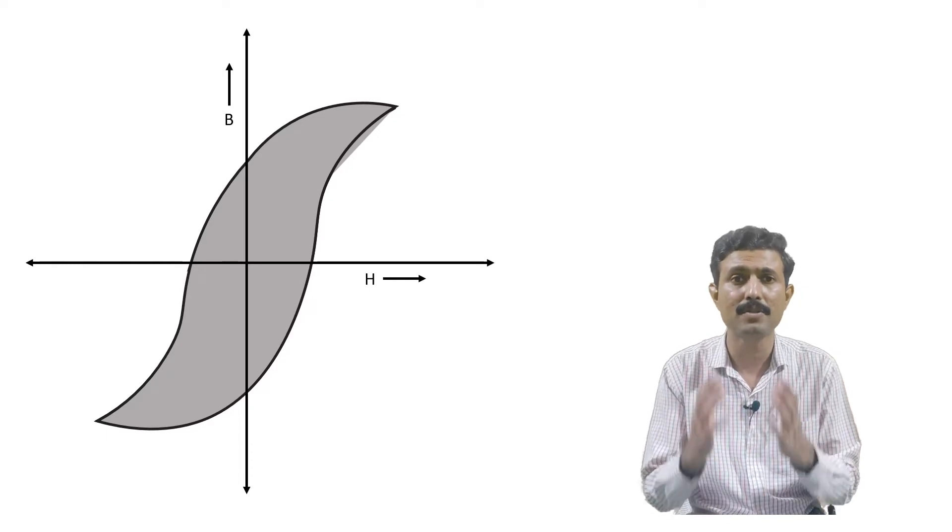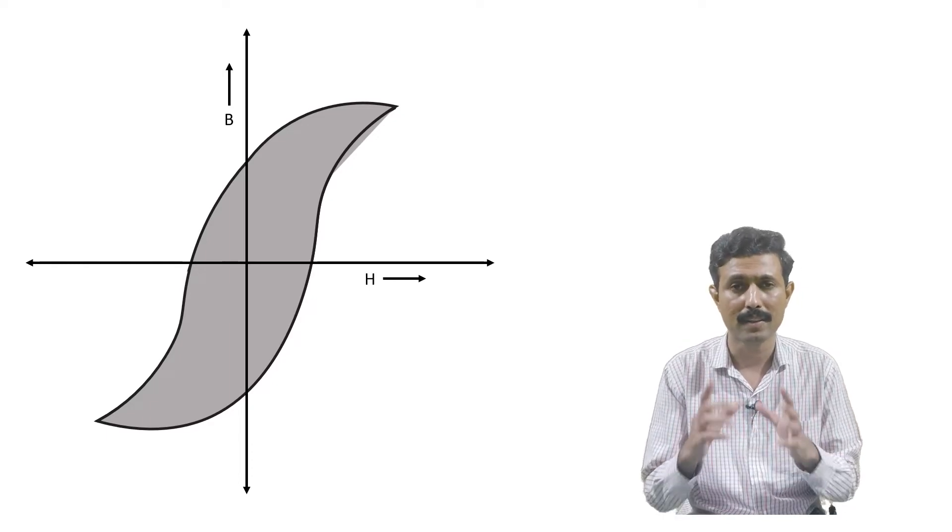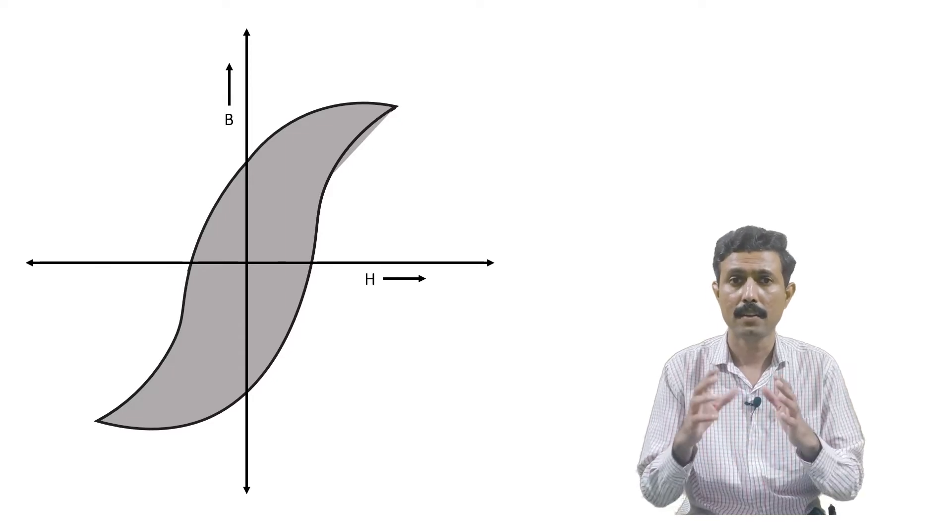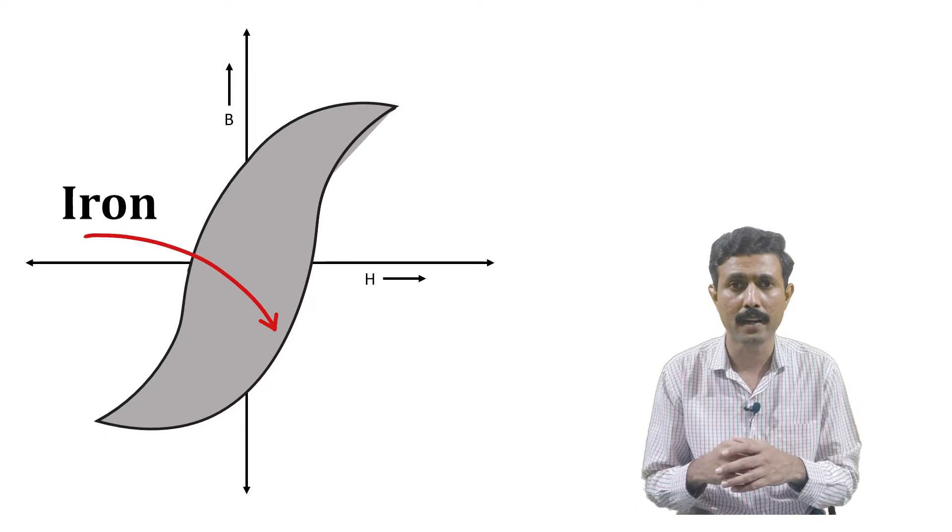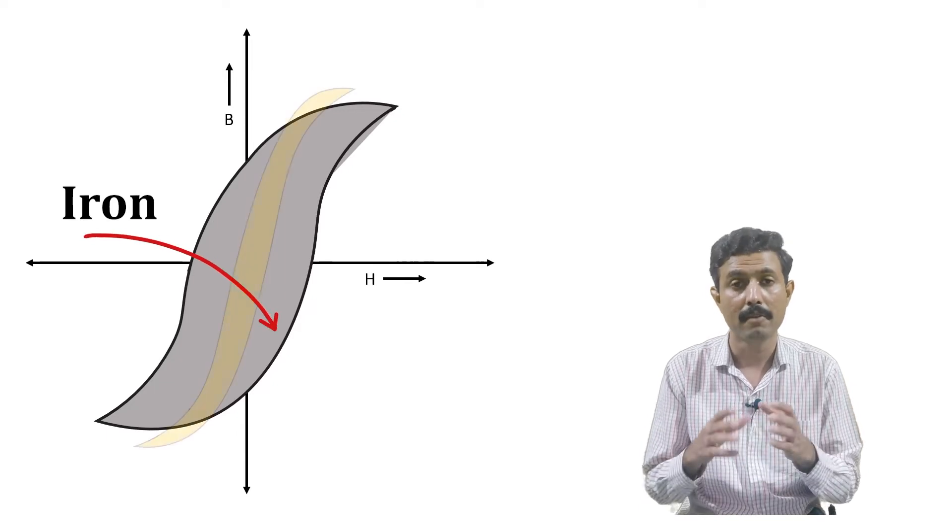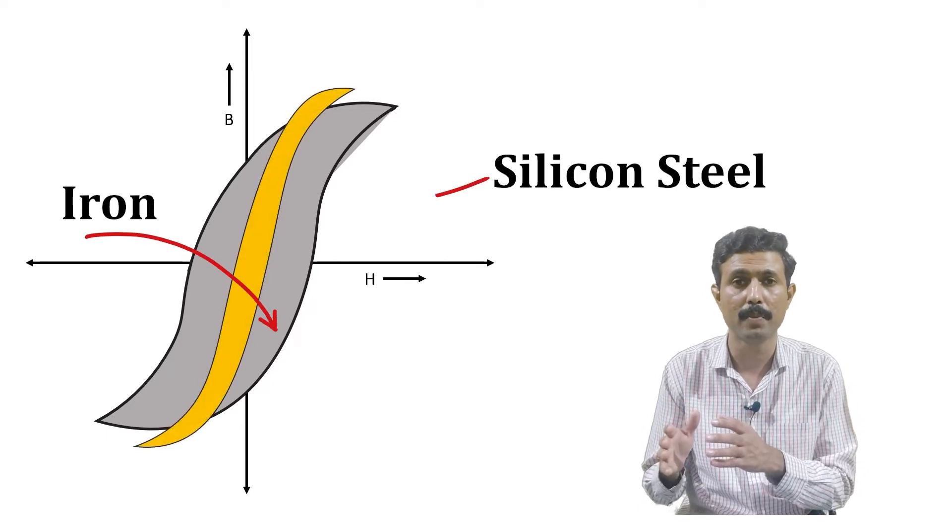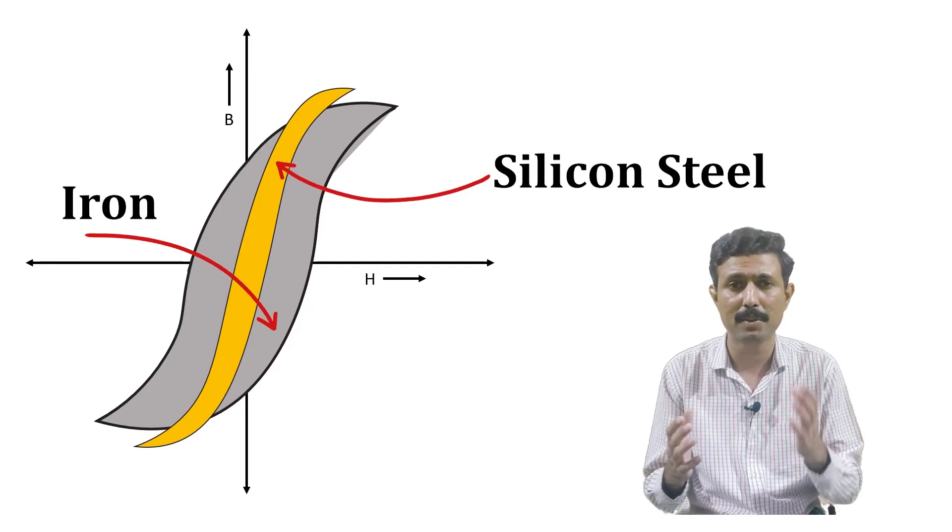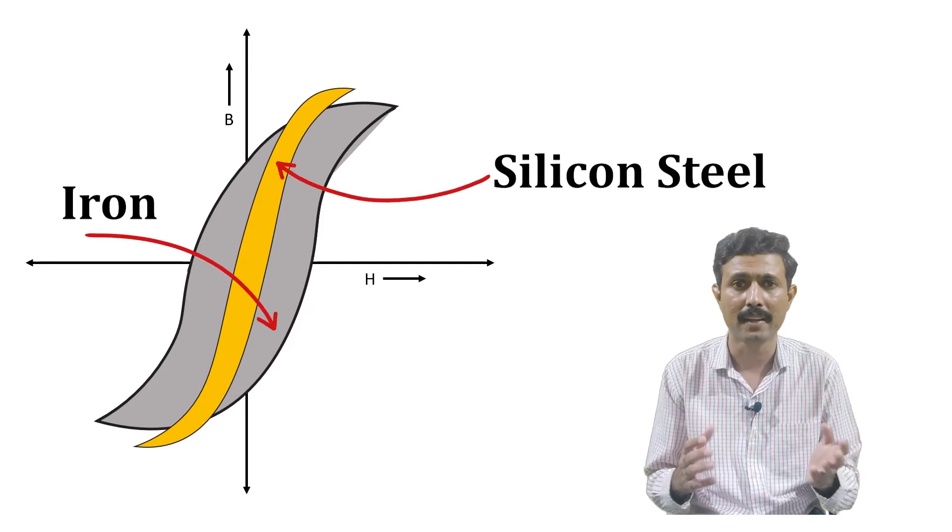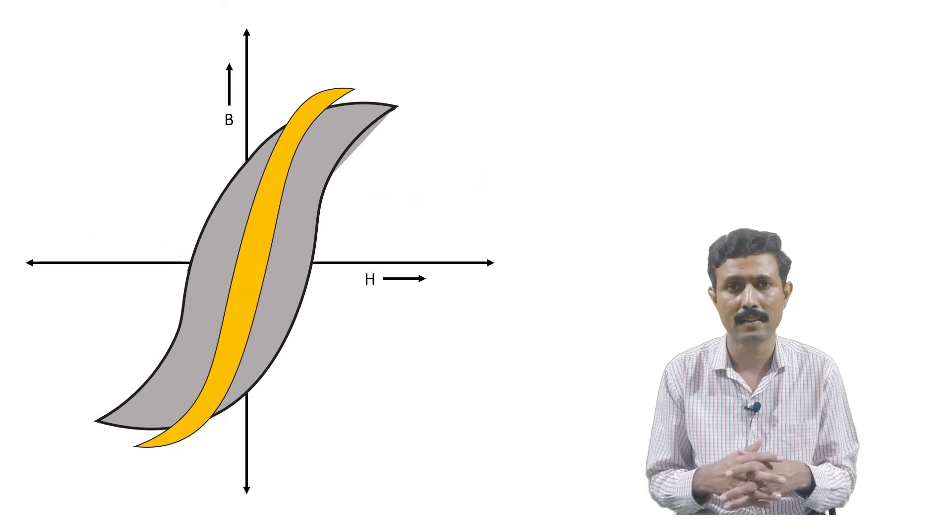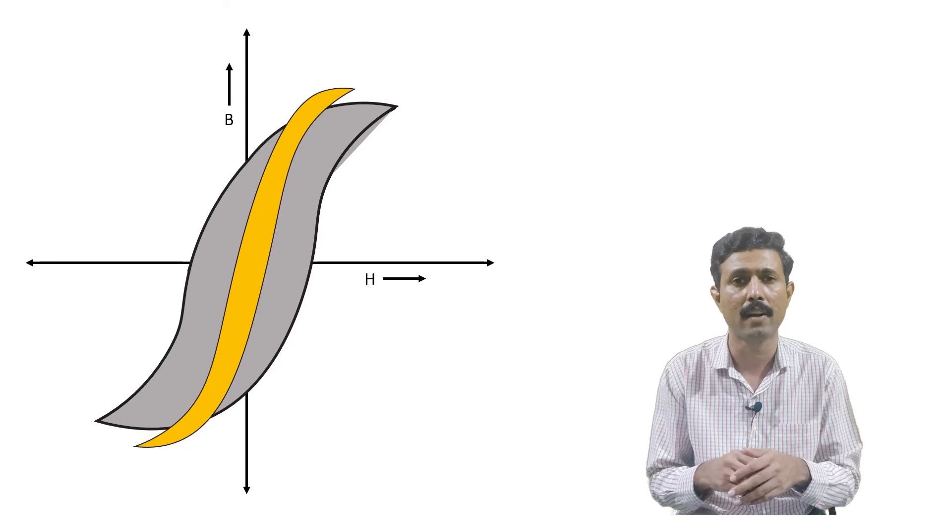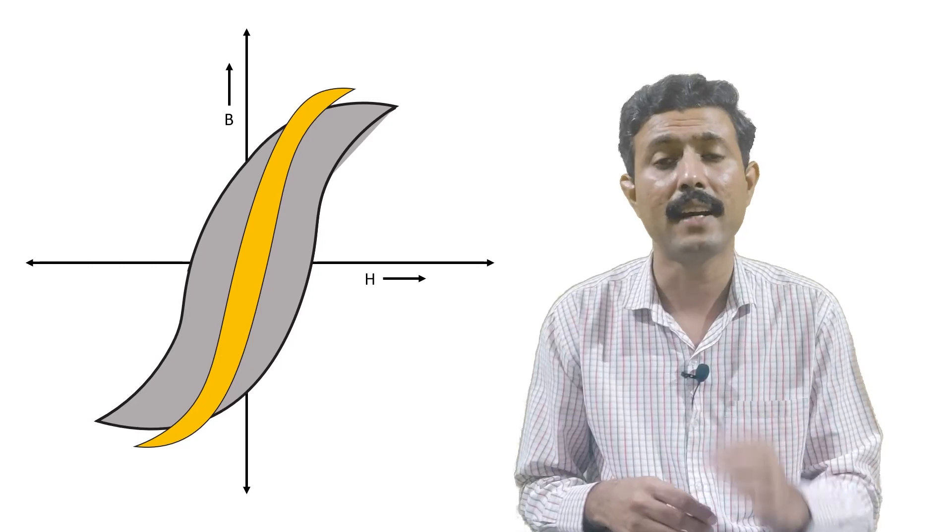So now how we can reduce the hysteresis loss? To understand that thing, let me show you the hysteresis loop of two materials. The first one is the hysteresis loop area of iron material, whereas the second one is the hysteresis loop area of silicon steel material. You can easily see the difference between hysteresis area of iron and silicon steel. The hysteresis area of silicon steel material is much smaller than the hysteresis area of iron material.